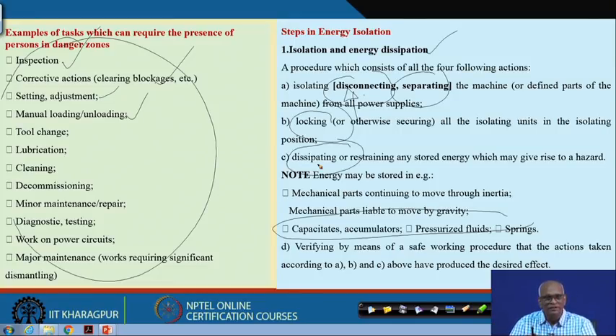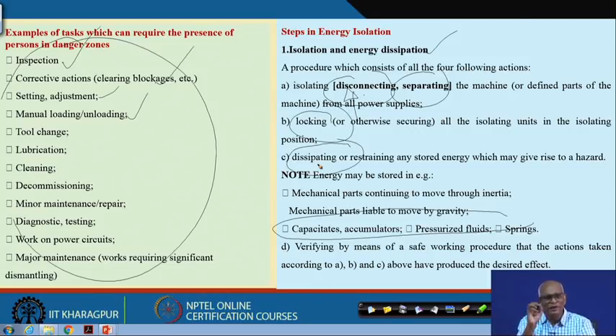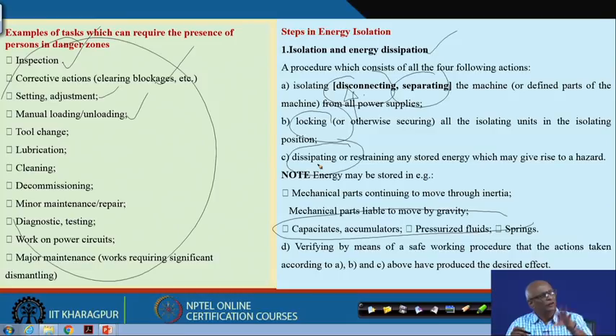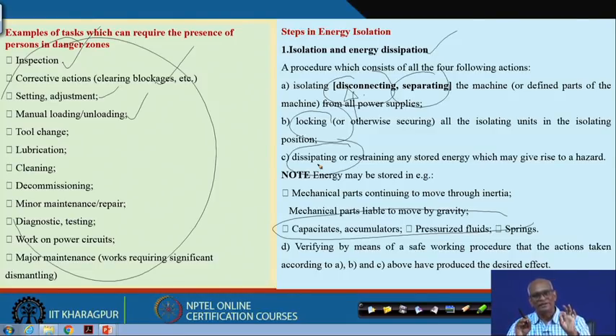Is it over with that? No. Afterwards you have to verify — by means of various techniques — whether isolation has happened 100 percent. What you intended, you have to verify: verify through procedures, verify through gauges, verify through testing — then you can start the job. This is the complete process of energy isolation.